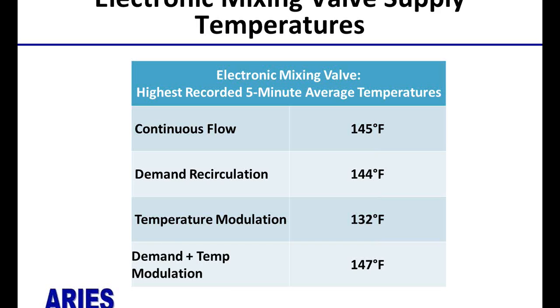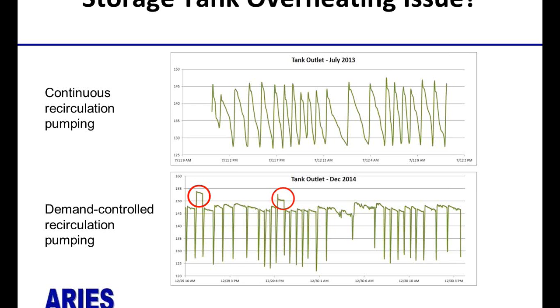Speaking to the electronic mixing valve issue of potentially sending out dangerously hot water with non-continuous flow, we didn't have fine enough data. We had 5-minute average temperatures to look at, where we are going to take maybe 10 second interval data and get a better picture of this. But you can see here that both with continuous flow and with the demand recirculation pump controls, you're getting temperatures that are well above that 125 degree set point. So something we'll be looking at in the future.